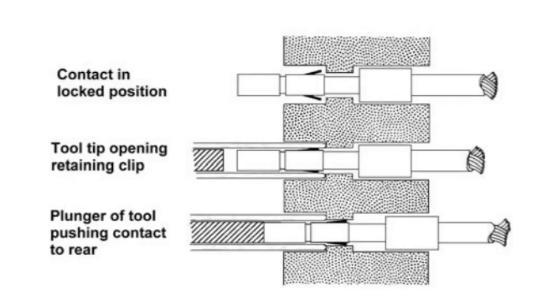On a contact lock, the locking device is located on the contact itself in the form of a spring finger, which snaps into place on a ring inside the insert. The contacts are usually inserted from the rear of the connector and removed from the front of the connector.